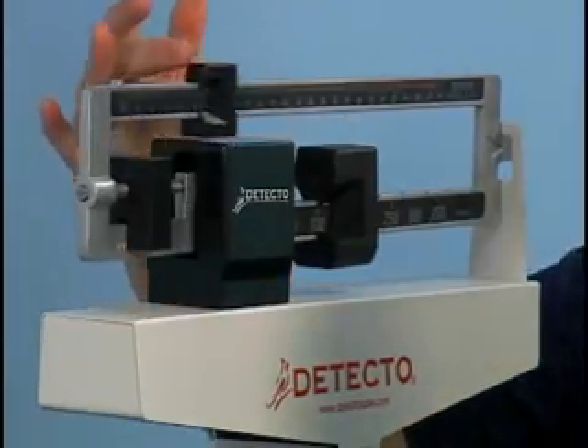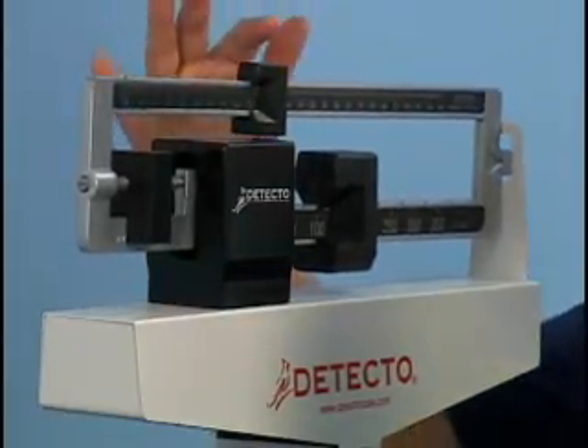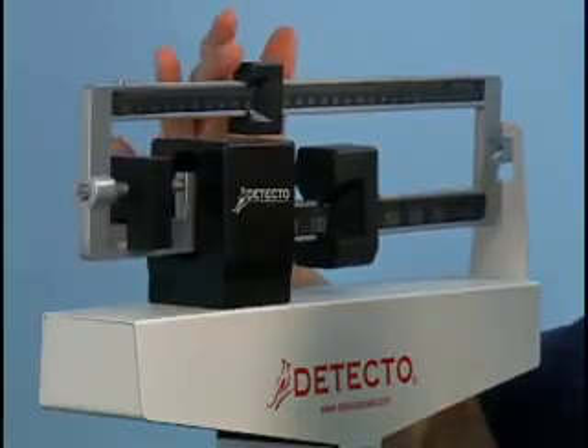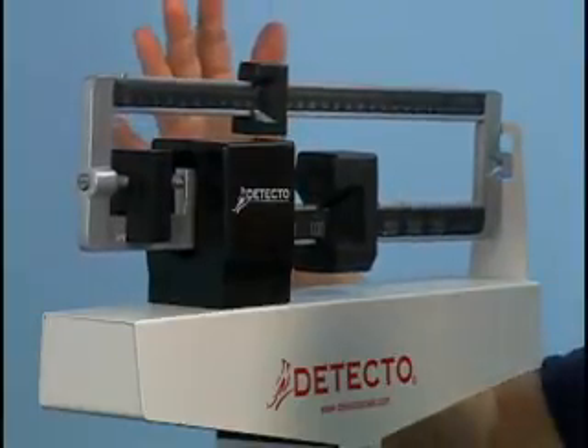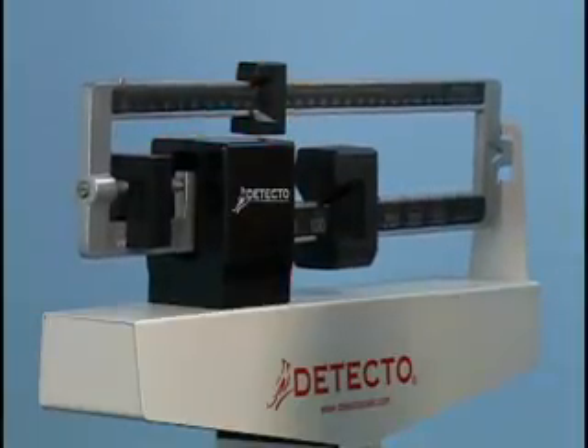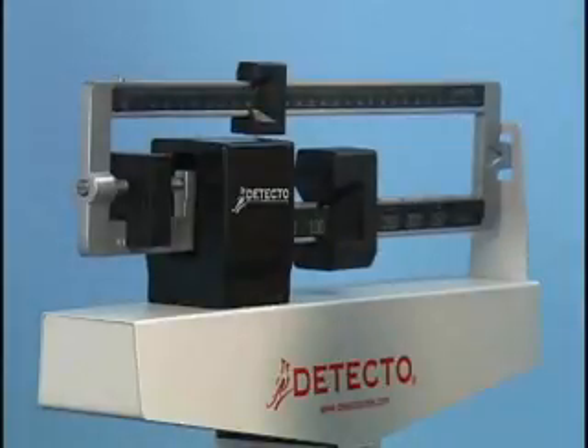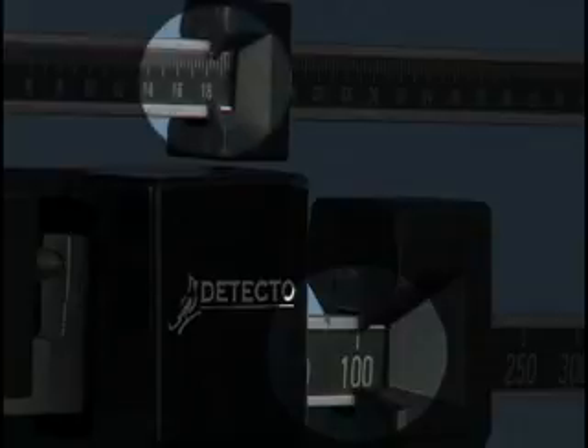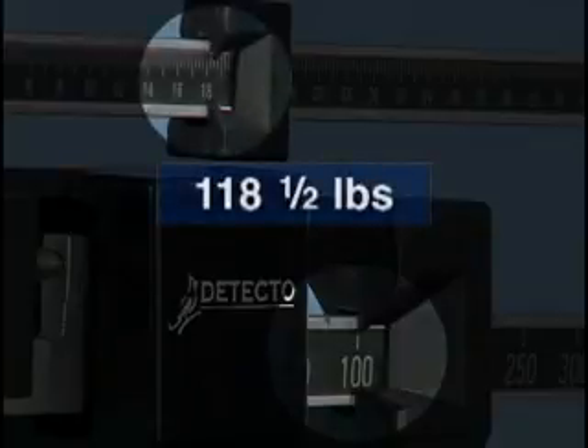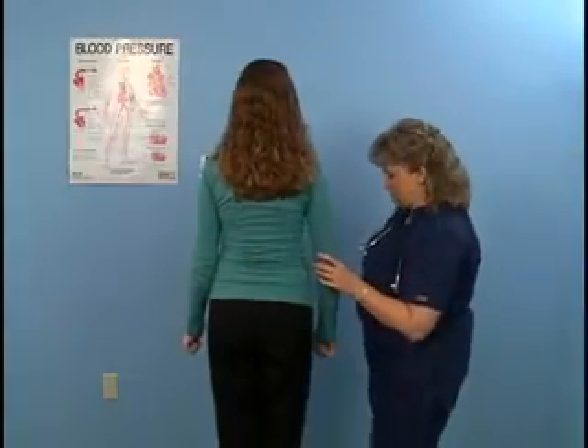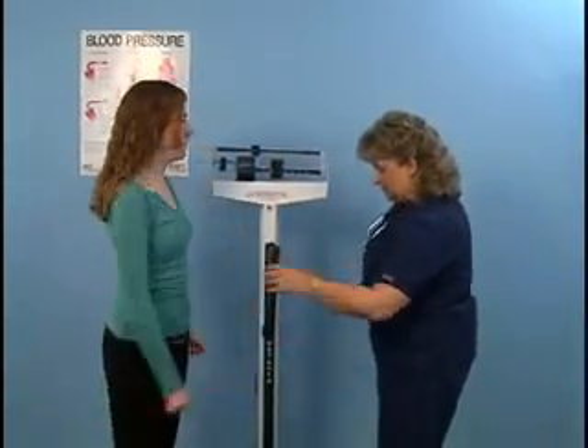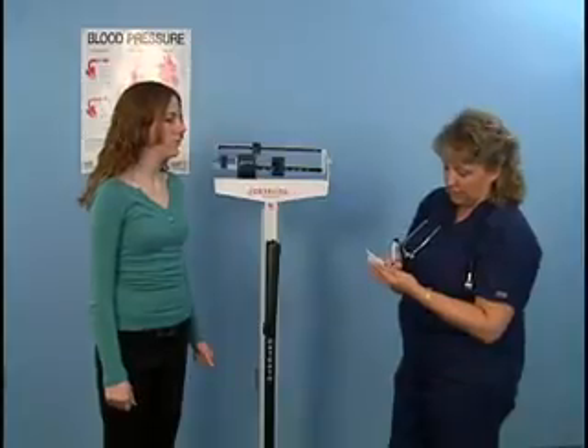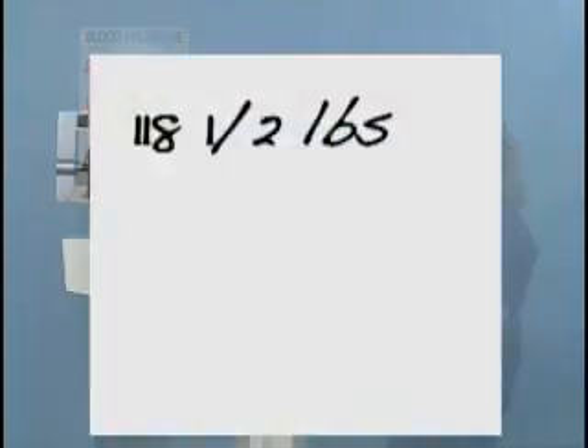Slide the upper weight slowly along its calibration bar by tapping it gently until the indicator point comes to a rest at the center of the balance area. Read the results to the nearest quarter pound by adding the measurement on the lower scale to the measurement on the upper scale. The patient weighs 118.5 pounds. Ask the patient to step down from the scale. Provide assistance if needed. Jot down this value or make a mental note of it.